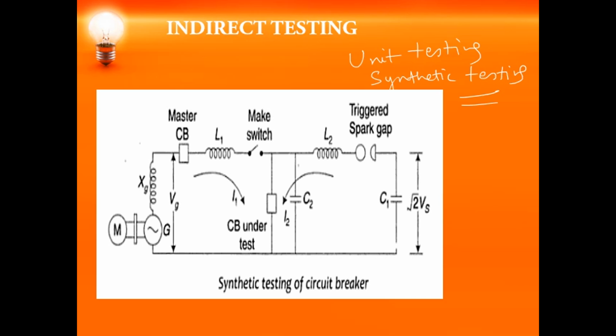Suppose you test one particular unit, that means you say that the entire circuit breaker is proper. That is unit testing. In synthetic testing, you have two separate sources instead of one: a voltage source and a current source. The current source is a high current, low voltage source, and it supplies the short circuit current. The voltage source is a high voltage, low current source, and it provides the restriking and the recovery voltage. There are two methods of synthetic testing: series testing and parallel testing. Of these, the parallel current injection method is widely used because it is capable of providing the restriking voltage and the recovery voltage as required by the different standards.